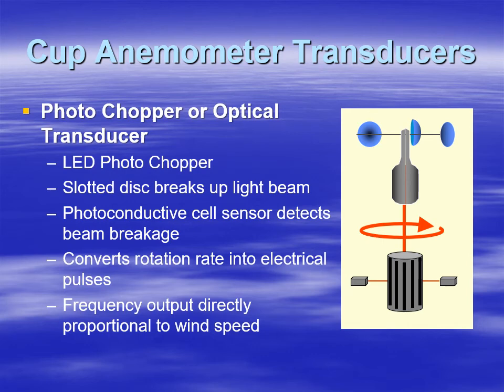The third type of transducer is a photo chopper or optical transducer, and this is where you have a light emitting diode that is shining through a slotted cup or a slotted cylinder, and the cylinder is attached to the shaft. As the shaft rotates, those slots are rotating around with the cylinder, and if you point that light emitting diode at the rotating cylinder, then eventually the slots will line up and allow the light to pass through at certain times, and other times it'll be blocked. So based on the number of times that it gets a hit of light over a period of time, it can figure out the rotation rate, and from that it can figure out the wind speed.